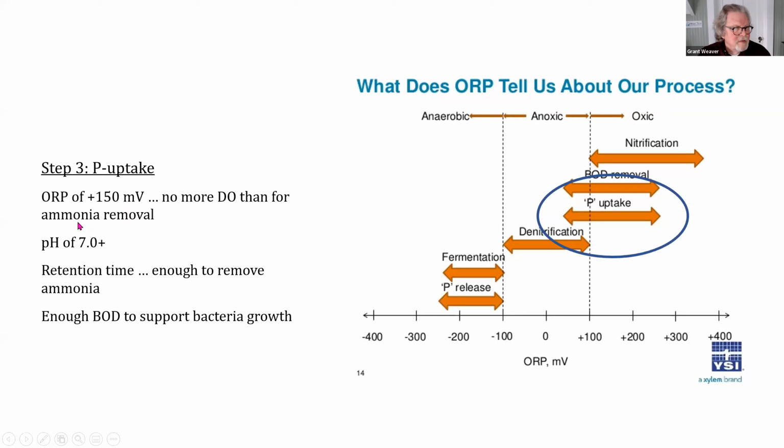This is a real nut here, maintaining a pH. And I've seen facilities where the actual pH I've seen, that's the light switch, is 6.8. So if the pH drops to 6.7 for one day, typically the biological phosphorus removal for that day stops. Gets back up above, the biological phosphorus removal will return. If it stays too low, too long, the phosphorus removal bacteria die off, and they're kind of slow growing little critters. It may take you a month or 6 weeks for it all to grow back.